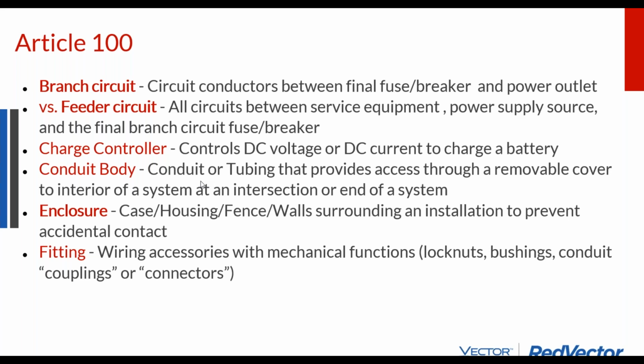And so, the general rule with solar and batteries is that this equipment needs to be fully enclosed, or if you're building your own battery bank and you're just putting the batteries on shelves, that area of the room needs to be enclosed. Just because an installer is putting a Tesla Powerwall on the wall of their garage does not mean that you can also put a bunch of batteries up on the wall. So there are enclosure requirements to prevent accidental contact. And if you're inspecting something and you're concerned about accidental contact, you would want a dead front on your boxes.